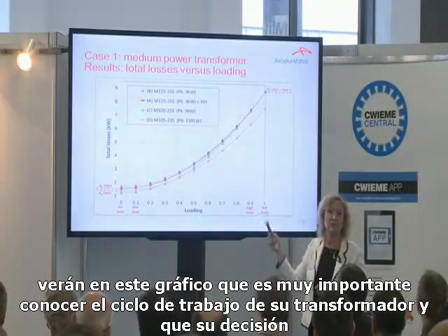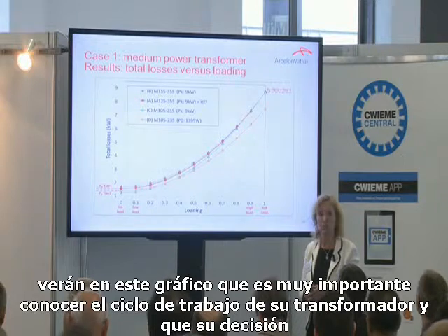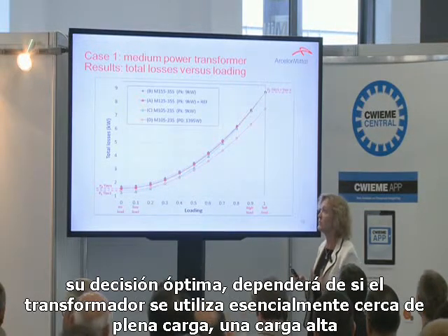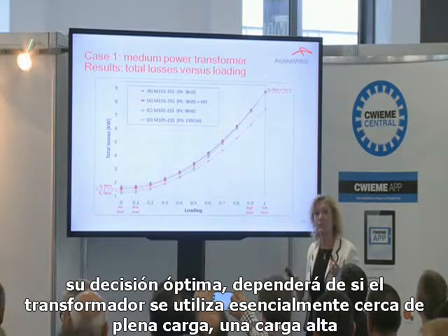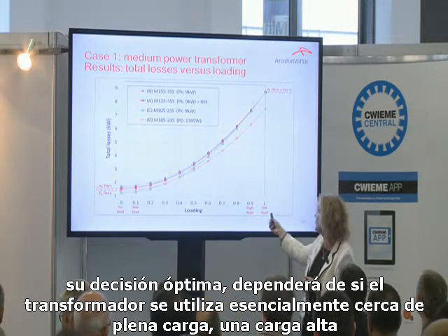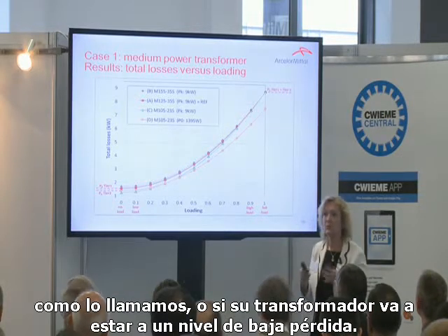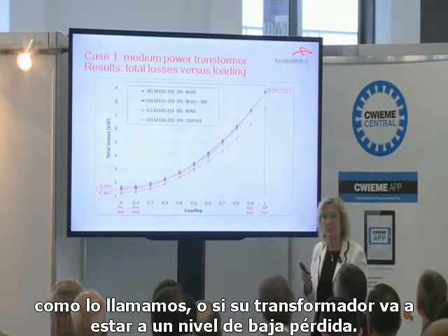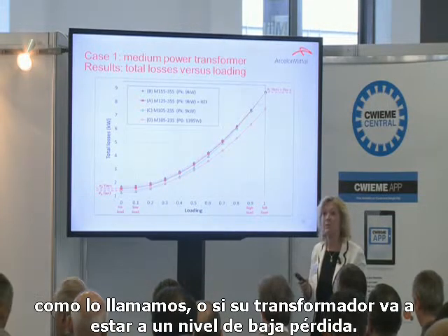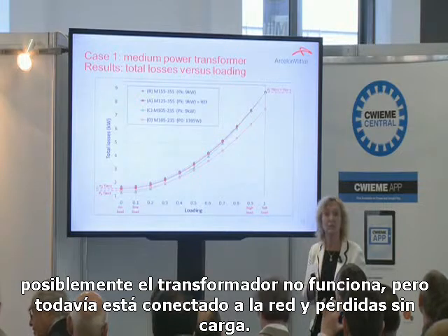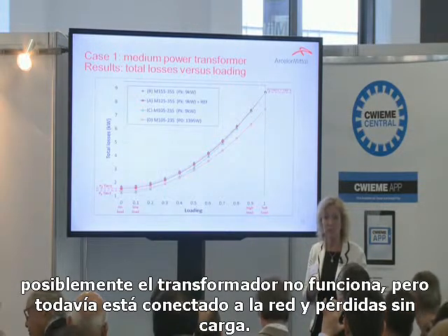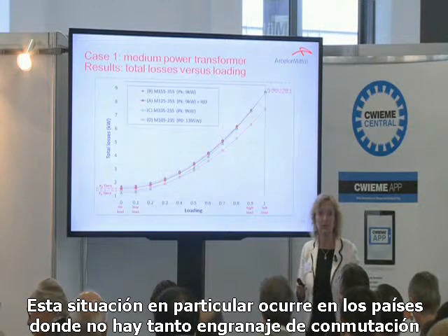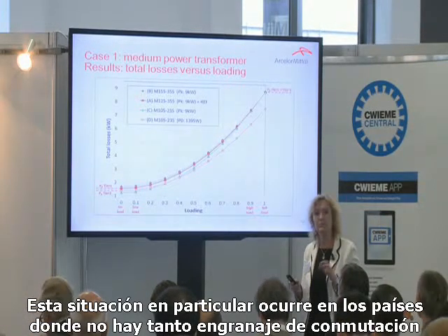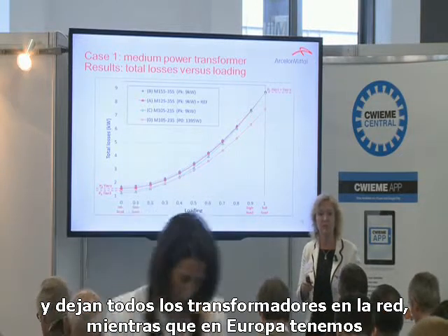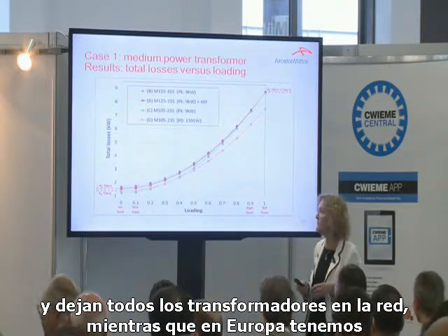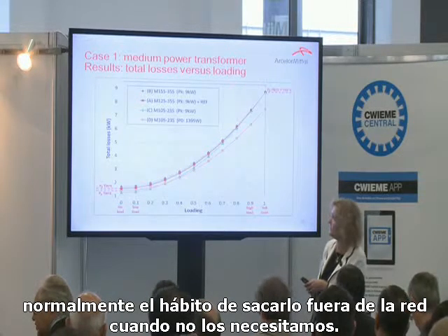You will see from this graph that it's very important to know the duty cycle of your transformer, and that your optimal choice will depend on whether your transformer will be used essentially at close to full load, high load as we call it, or if your transformer is essentially going to be at a low load level, or possibly also the transformer doesn't work but it's still connected to the grid and it will consume no load losses. This situation is in particular used in countries where there is not so much switching gear and they leave all the transformers on the grid, whereas we in Europe have normally the habit of taking them off the grid when we don't need them.